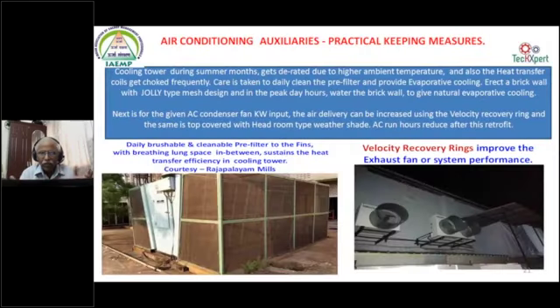Coming to the auxiliaries of the air conditioning, the cooling tower needs clean surroundings. One is keeping the surroundings clean, the other is putting a mesh so that it is clean daily and you are maintaining it. And in some industries, we have also suggested a brick-type, jali-type mesh wall, and just put your RO water or clean water on it in the peak hours of the peak days of the summer. It's natural evaporative cooling. The air is sucked in through the brick wall with the jali-type mesh, which is fixed with a breathing space, so that air is sucked in and the cooling tower function improves by taking advantage of the wet bulb of the ambient. The cooling tower can then operate well with a better range and approach.